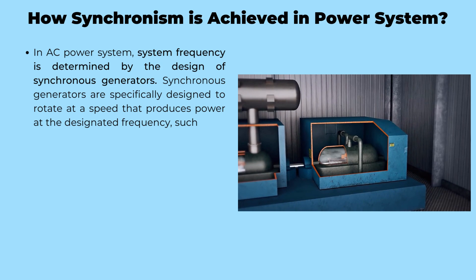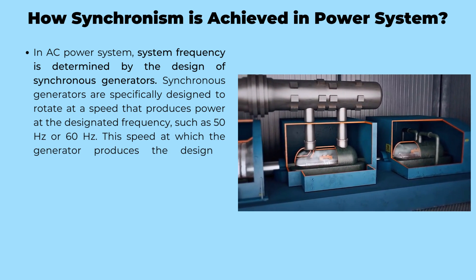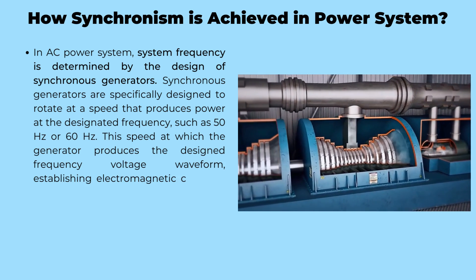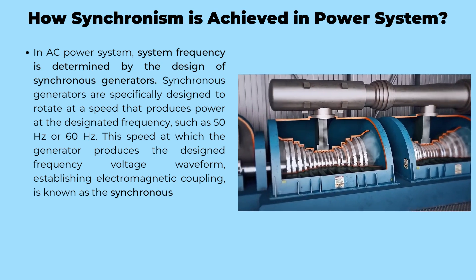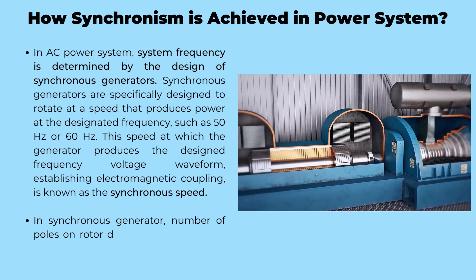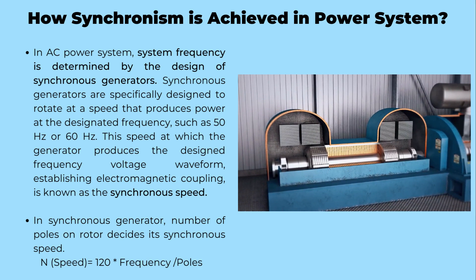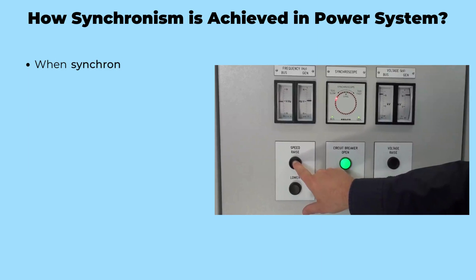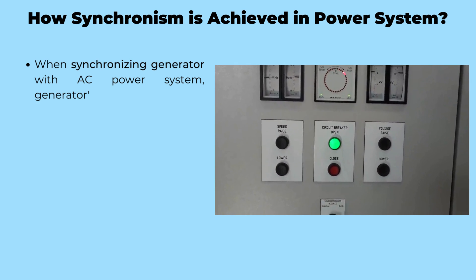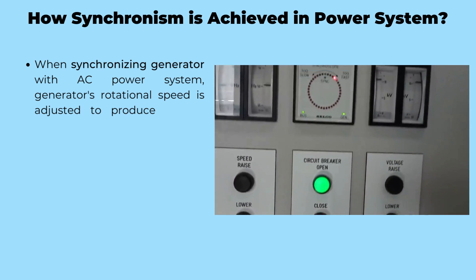This specific speed, known as the synchronous speed, establishes an electromagnetic coupling, paving the way for synchronization. The synchronous speed of a generator is determined by the number of poles on its rotor. These poles dictate the rotational speed required to produce a voltage waveform with the designated frequency. It's through this synchronized rotation that the generator can seamlessly connect with the AC power system. Synchronizing a generator with the AC power system involves a careful adjustment of its rotational speed, aligning the generator's frequency and phase angle with that of the power system.